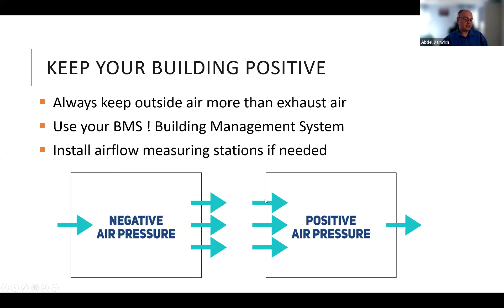And really the key takeaway to avoid having smoke get in is to keep your building positive. Again, it's simple physics: once you bring in more outside air than what you exhaust, your building will be positive. You can use your building management system and install airflow measuring stations so you can measure the flow of air coming in and the flow going out, and make sure that the air coming in is more than the air going out.